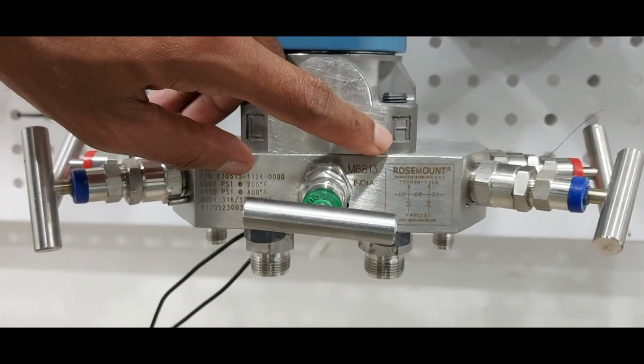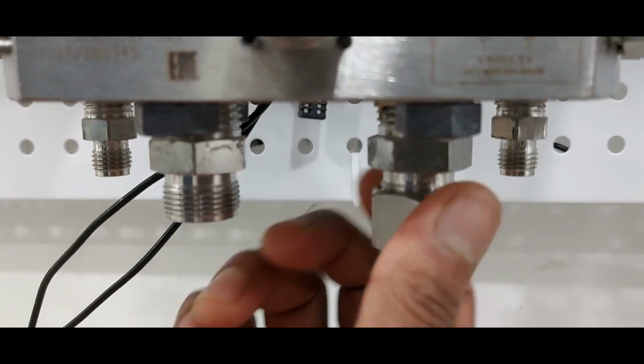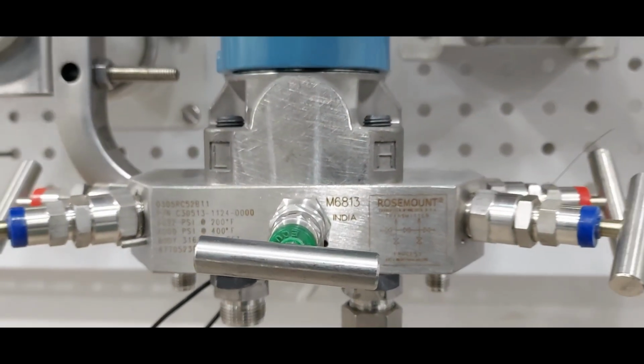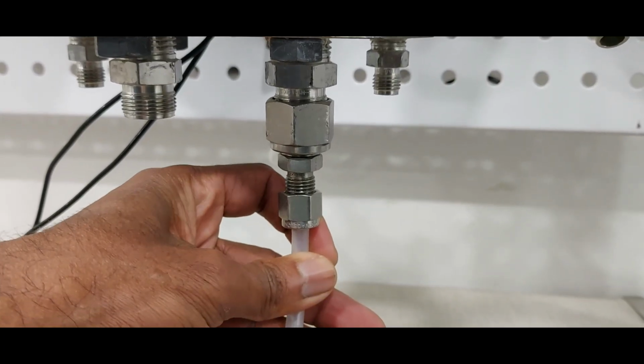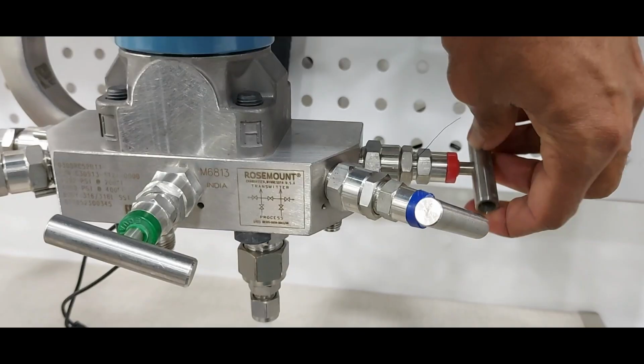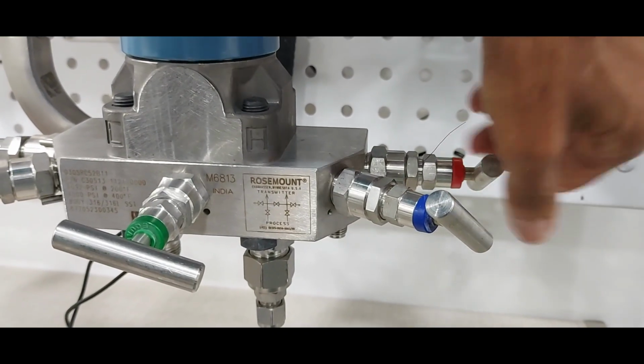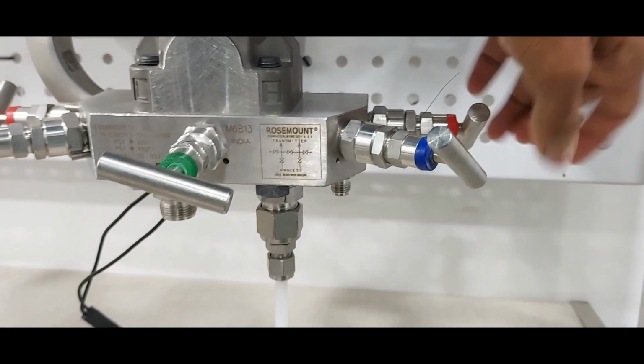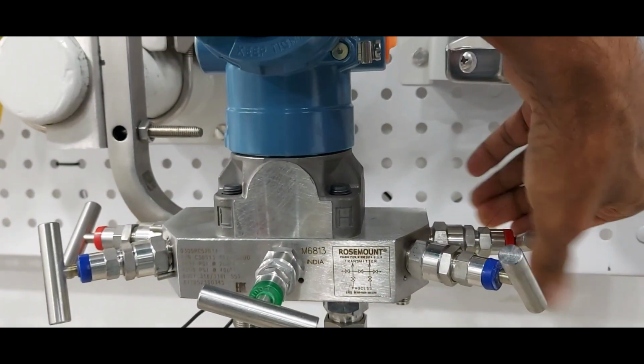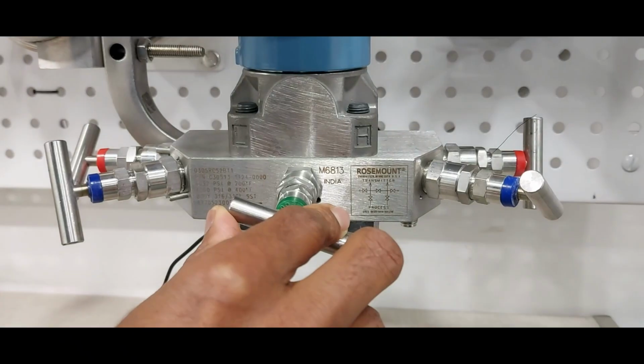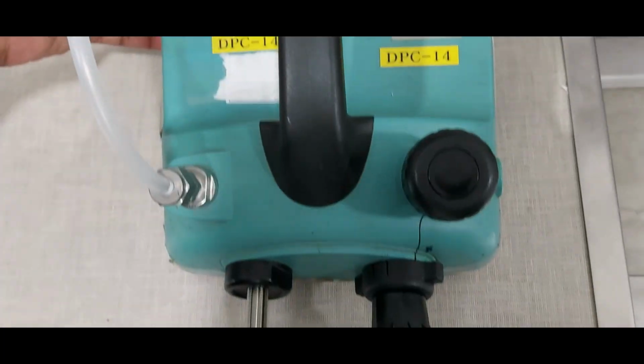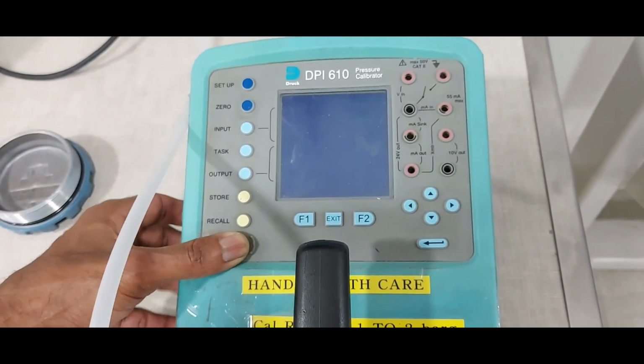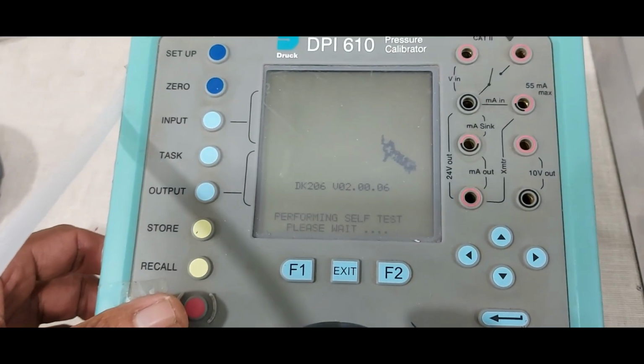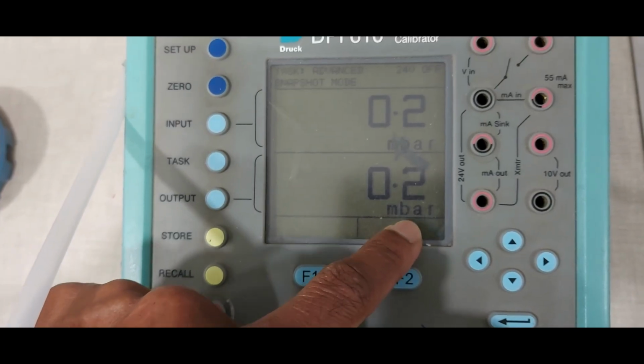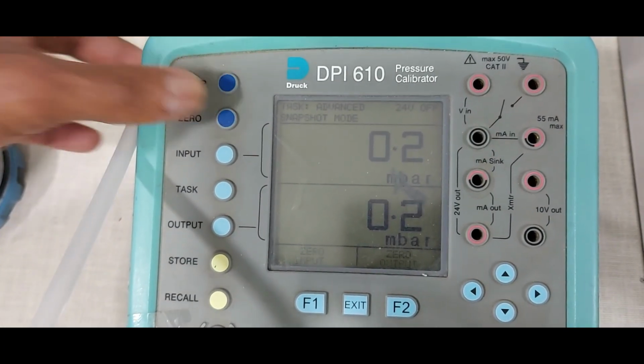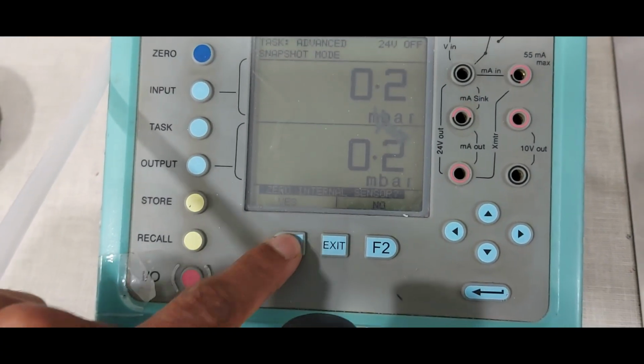Next connect the fitting from the high side. High side connected. Next we are connecting the pressure calibrator line. Close the vent valve, high side. Now fully close it. Next close the equalization valve. Next power on the pressure calibrator. Unit is millibar, already selected. Set it to 0 plus 0 and save it.